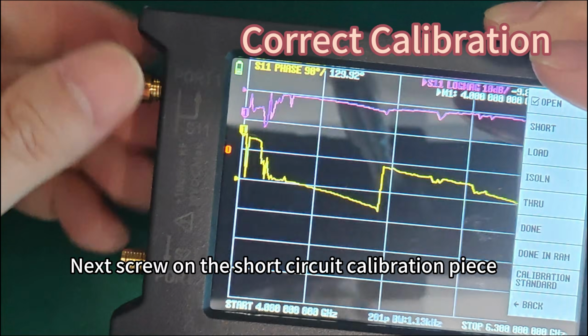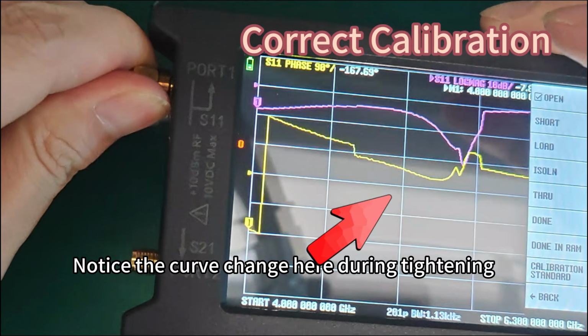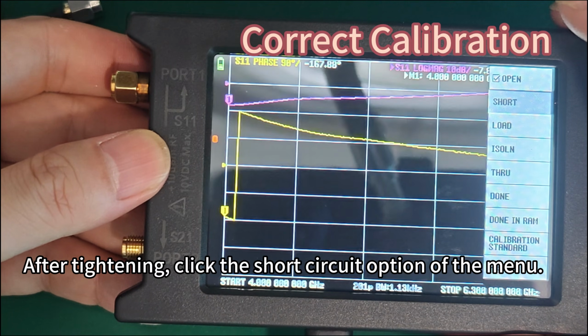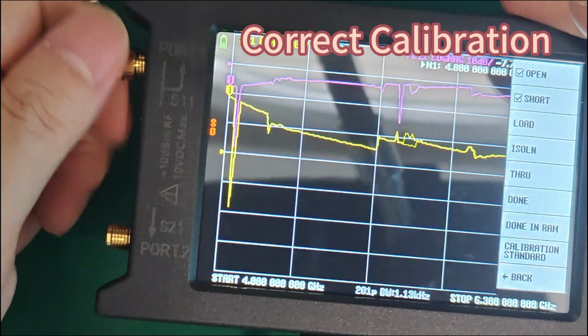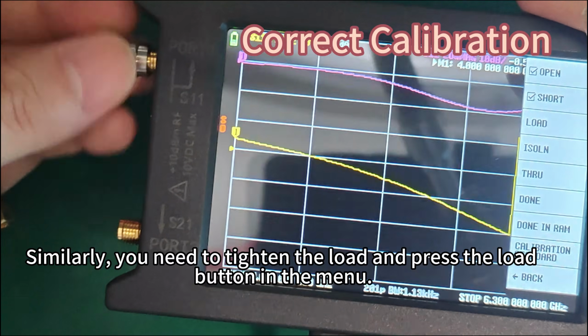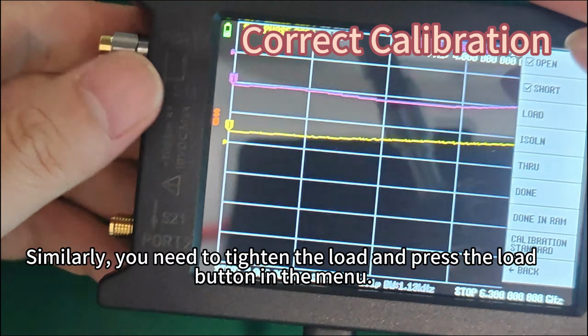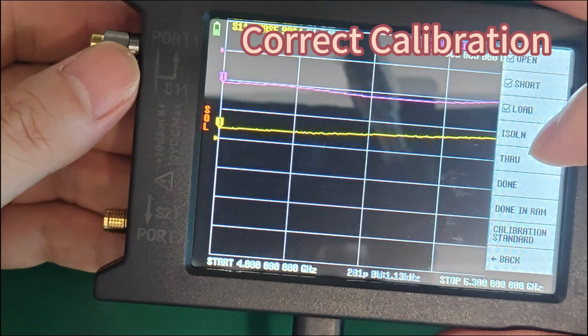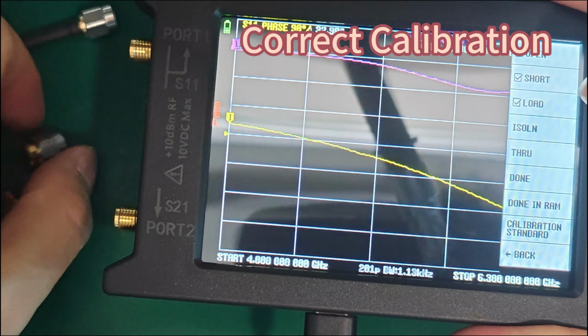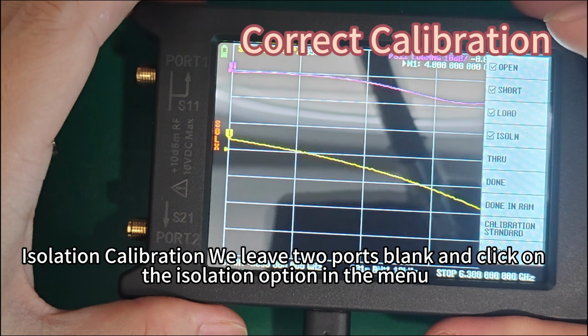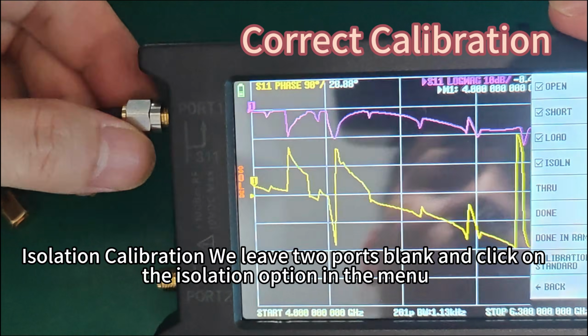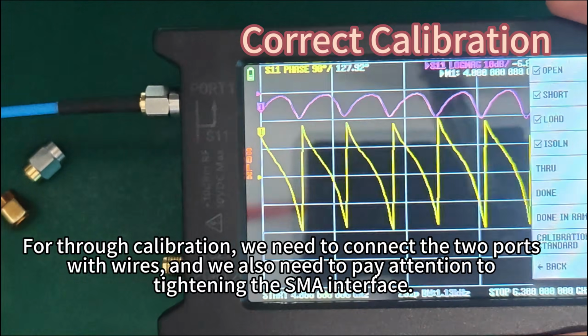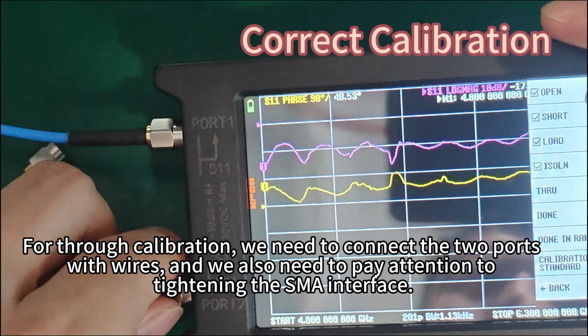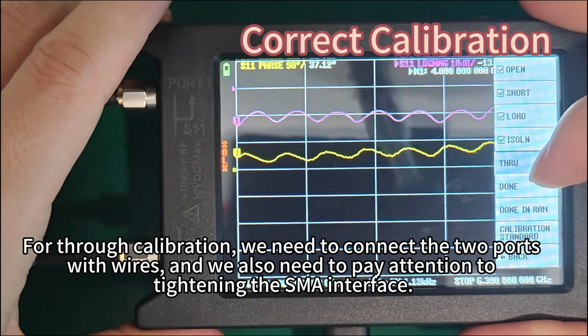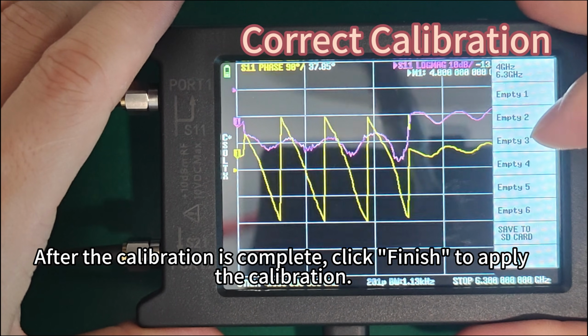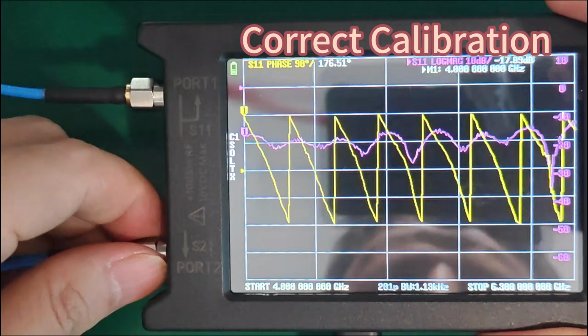Next, screw on the short circuit calibration piece. Notice the curve change here during tightening. After tightening, click the short circuit option of the menu. Similarly, you need to tighten the load and press the load button in the menu. Isolation calibration, we leave 2 ports blank and click on the isolation option in the menu. For through calibration, we need to connect the 2 ports with wires, and we also need to pay attention to tightening the SMA interface. After the calibration is complete, click Finish to apply the calibration.